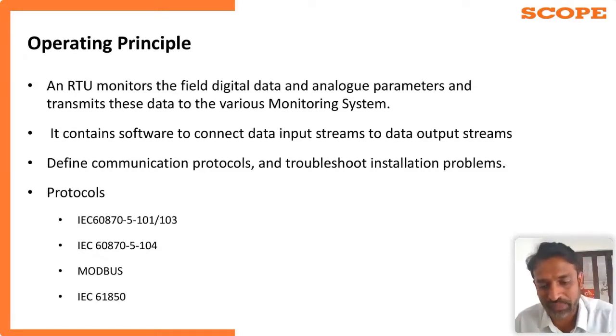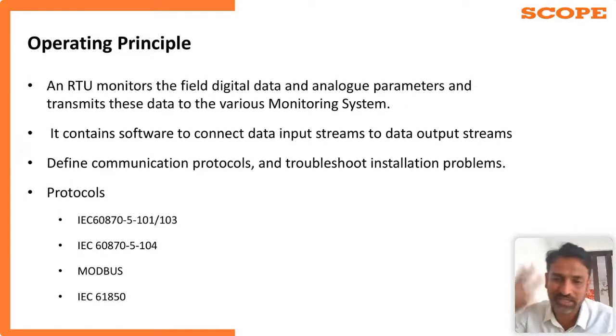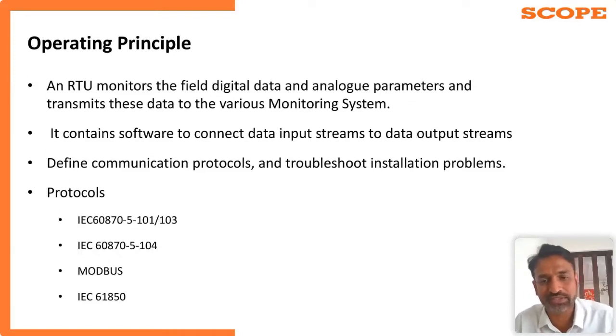So when you are making or purchasing any RTU, you have to look into these two or three aspects. One is how many DIs you require, how many DOs you require, and what is going to be operated with this RTU. And the most important is what communication you require from the substation side and the remote side. These two protocols will also be very important for the RTU configurations.